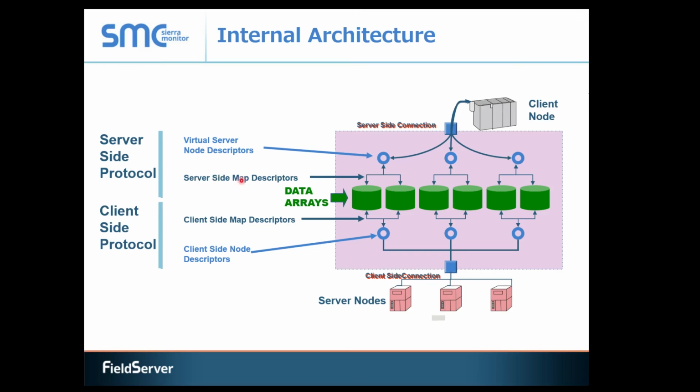So that's the purpose of our server-side mapping. And our server-side mapping will say this piece of data over here in this data array can be represented as, for example, analog input 1 on, for example, device instance 11. And that's what our server-side mapping will do for us. It will just represent each of the pieces of data, maybe add some properties to it so that it makes it very readable. And then when our BACnet device comes and says, please give me device instance 11, analog input 1, we'll go, well, that's that piece of data over here. Here, have it back with all the properties we've declared as well. And then we're finished mapping all of our data.